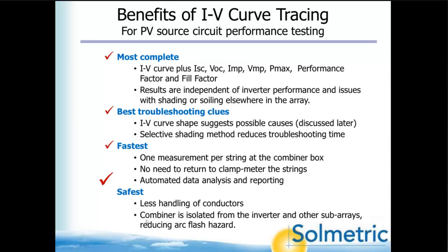of doing something that would get you in trouble. And probably more importantly, when you're doing curve tracing, your combiner box is isolated from the inverter and the other subarrays. So you have much less of an arc flash hazard than you do in the case where you're working with a clamp meter inside of a live combiner box that's fully connected to the rest of the system. If you have not read the recent article on flash hazards in SolarPro, I strongly encourage you to do so.